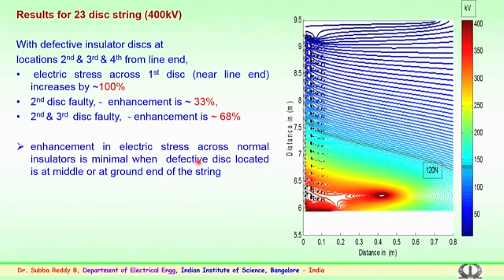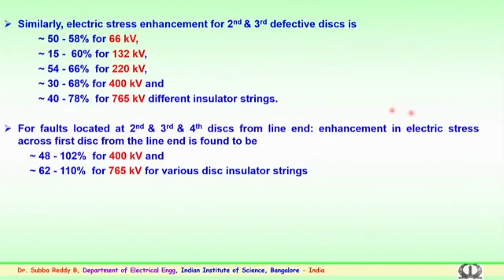So, the enhancement in electric stress across the normal insulators is minimal when defective insulators are located, as mentioned earlier, at the middle, that is, in case of 23 discs in a string. After the 13th, 14th, 15th and at the ground end, not much of an impact or electric stress is seen. So, this is one of the important points to be noted.